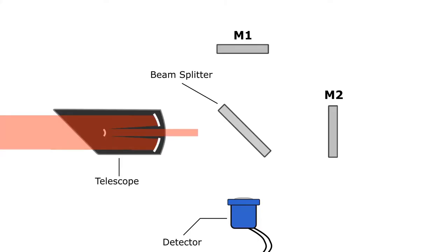An interferometer takes a beam of light, splits it into two beams, then reflects those beams from two separate mirrors back to the beam splitter where they're recombined to form the final beam which is then sent to the detector.